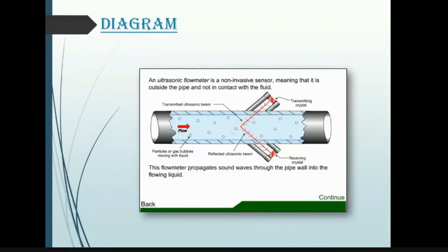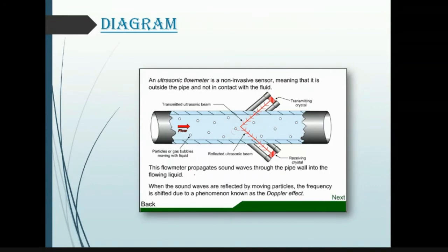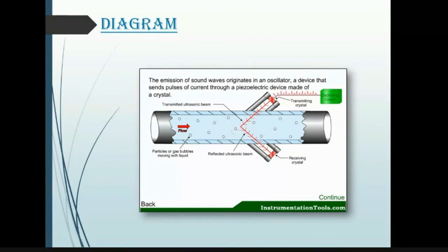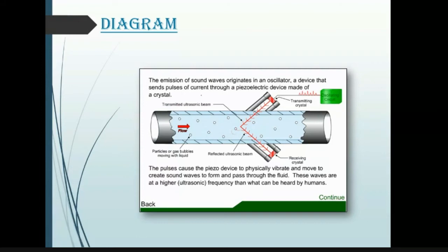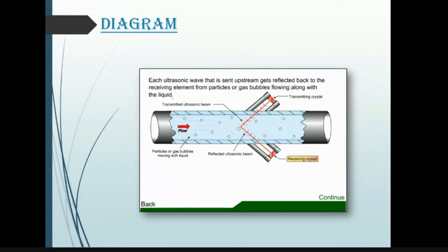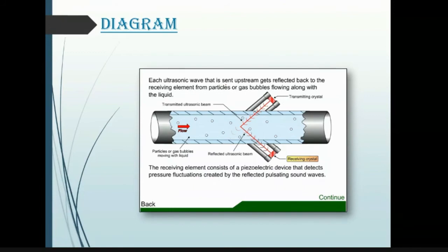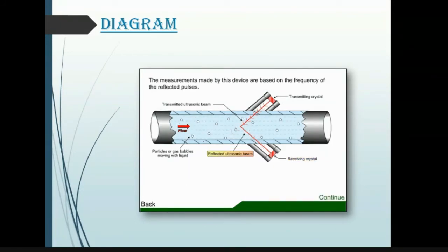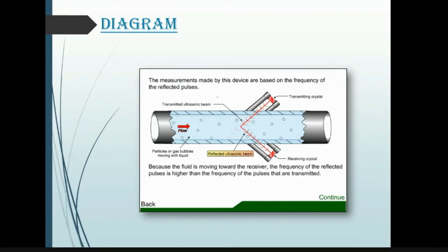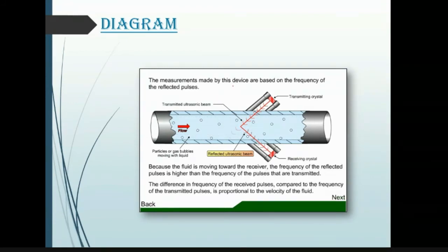This flow meter propagates sound waves through the pipe wall into the flowing liquid, and the sound waves are reflected by moving particles. The emission of sound waves originates in an oscillator, a device that sends pulses of current through a piezoelectric device made of a crystal. The pulses are transmitted upstream in the flowing liquid. Each ultrasonic wave sent upstream gets reflected back to the receiving element from the particles or gas bubbles moving along with the liquid, and the transducer converts the sound. The measurements made by this device are based on the frequency of reflected pulses.